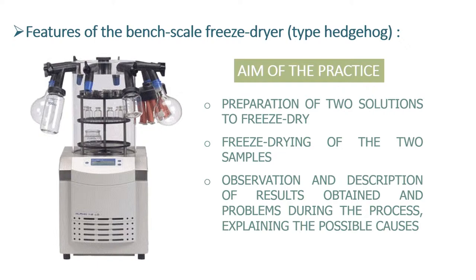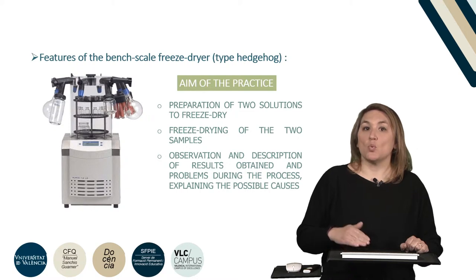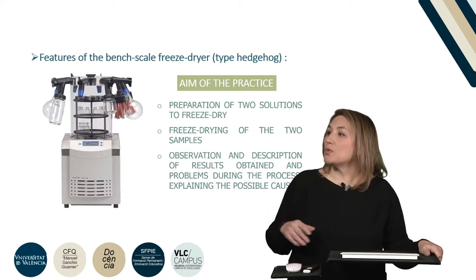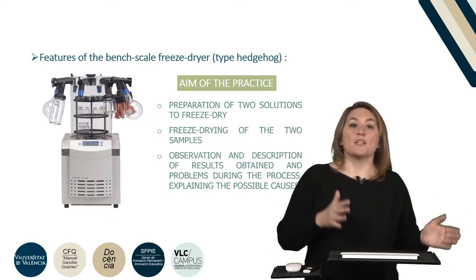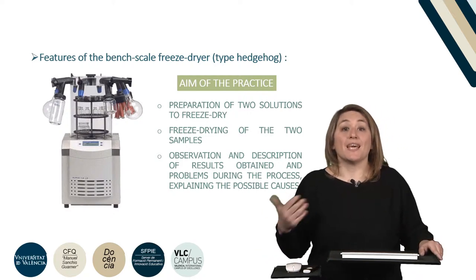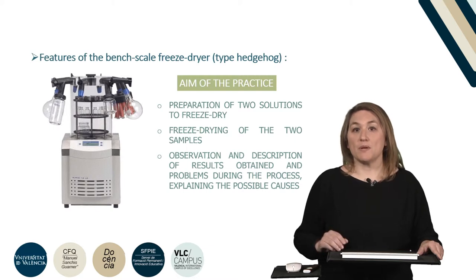Another point to keep in mind is that freeze drying is an endothermic process — it needs energy input to be carried out. In most cases, industrial freeze dryers allow the initial freezing and the subsequent sublimation of the solvent inside the same apparatus, supplying the energy by heating through the tray where the bottle is placed. However, most apparatus working at small scale have at least two different characteristics: the product must be introduced already frozen, meaning the freezing phase is carried out in another device, and the heat necessary to sublimate the solvent is taken from the environment, depending very much on room temperature.